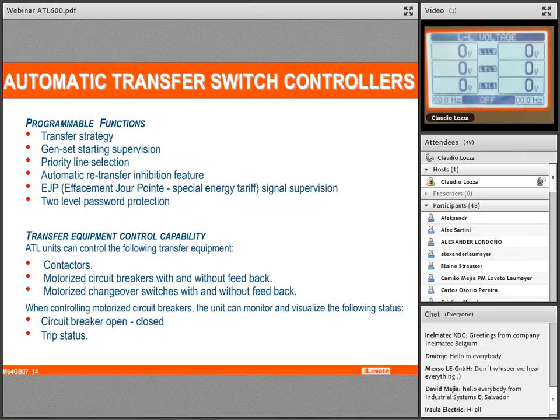I have information about the status of the genset. I have some signals for the feedback, so I can manage the genset status. So, for this application, we have a dedicated alarm that advises the user if the genset is not ready. With the controller, we can manage the most common equipment using this application: contactors, motorized circuit breakers, and the motorized changeover, all with or without the feedback. So you can set up the controller according to your actual necessity.